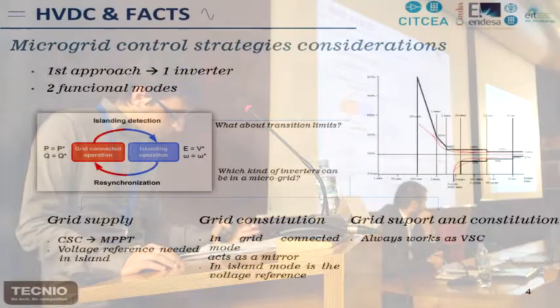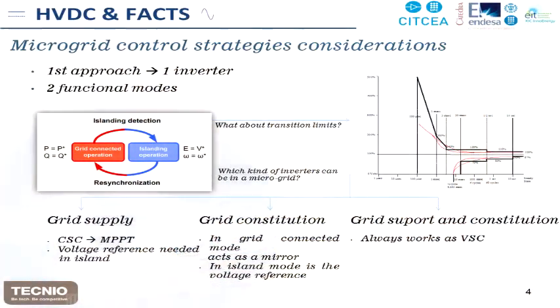On the other hand, which kind of inverters are we going to find in a microgrid? From a control perspective, we can say that three strategies appear. The grid supply inverters are inverters that inject or deliver the maximum power they take from their source, such as photovoltaic inverters using MPPT algorithms. And it's really important to highlight that a voltage reference is always needed to operate that kind of inverter.